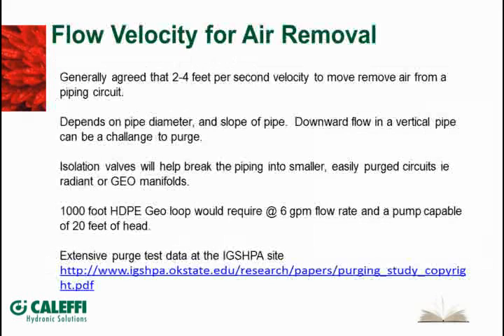So the industry agrees on 2 to 4 feet per second. That Purge Rate company that I met down there at the IGSHPA show said they'll go up to 6 feet per second is what they like to run for their velocities when they're purging their big systems. And, of course, it's going to depend on the size of the pipe that you're trying to purge out, the slope of the pipe. It's really hard to push air down a vertical pipe.